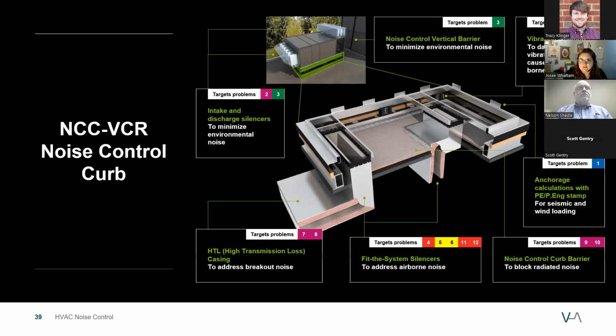According to the project's needs, a number of customizable solutions are integrated into the curb. These aren't simply standard options. This provides the engineer a single amalgamated solution to address multiple areas of concern with single source responsibility. So looking at this one here, you can see HTL casing, high transmission loss casing, to address breakout noise. Fit-to-system silencers address airborne noise. A noise control curb barrier blocks radiated noise. And anchorage calculation with PE stamp covers seismic and wind loading.